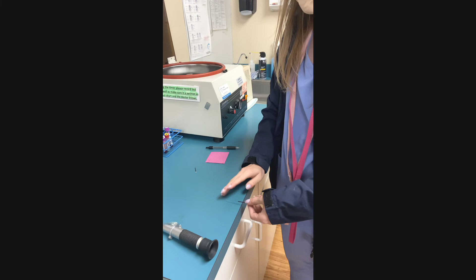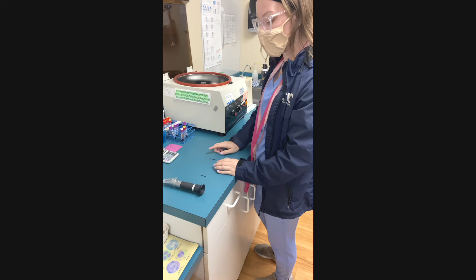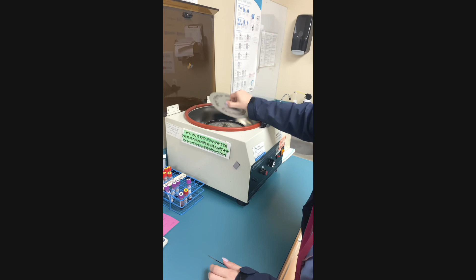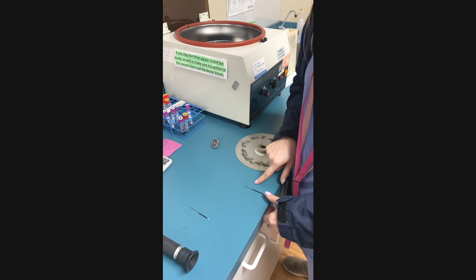And then with the other hematocrit tube, what you want to go ahead and do is place it in the incubator at 58 degrees Celsius for 3 minutes. So I'm going to go ahead and do that, and then after the 3 minutes are over, I'll come back for the next steps. Alrighty, so after it's done being in the incubator for 3 minutes, we're going to go ahead and take it out. And then we're going to come back over here. And before we get the total solids of this one, we're going to go ahead and centrifuge it again. So again, for our centrifuge, you have to centrifuge it on high for 5 minutes. So I'm going to go ahead and put this back in the centrifuge, and then we'll come back once it's done being centrifuged again.